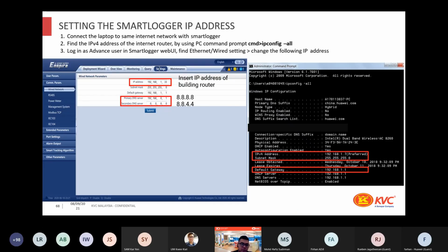Always remember, I would say this is the hardest part of commissioning, which is to set the Smart Logger IP address. A lot of times you're using a LAN cable to connect to the router. This is not as straightforward as the dongle solution, where you connect directly from the dongle to the router, because you need to do minimal setting to change the Smart Logger IP address to be in the same communication address as the router.